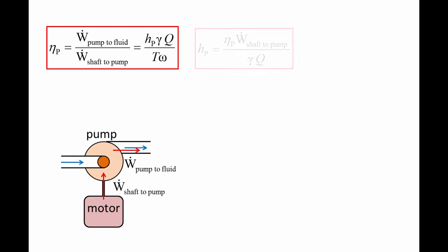The power transferred through the shaft to the pump is equal to the shaft torque, T, times the shaft's angular speed, omega. This equation can be rearranged to form the following relationship: the pump head is equal to the pump efficiency times the power transferred through the shaft to the pump, divided by gamma Q.